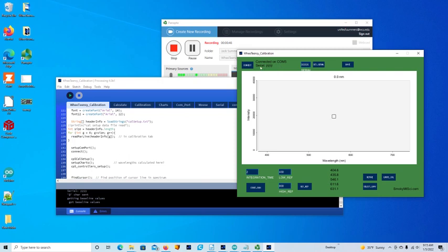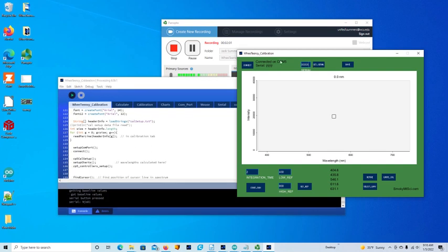Down here it says serial number, and this is what you get if there's no serial number in the EEPROM, right? There's supposed to be a serial number in your non-volatile memory. So let's just set a serial number. If we want to set the serial number, we come over to this box, we click in there, and we backspace until all the X's are gone.